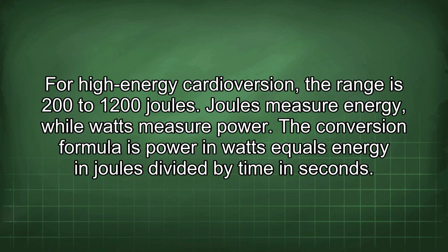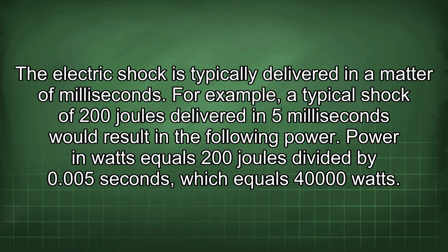Joules measure energy while watts measure power. The conversion formula is power in watts equals energy in joules divided by time in seconds. The electric shock is typically delivered in a matter of milliseconds. For example, a typical shock of 200 joules delivered in 5 milliseconds would result in the following power. Power in watts equals 200 joules divided by 0.005 seconds, which equals 40,000 watts.